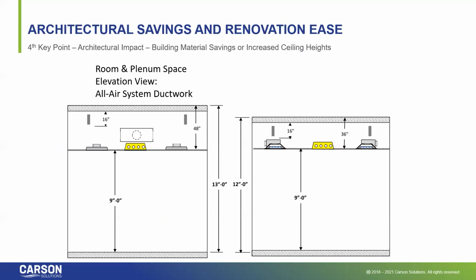From an architectural standpoint, both in renovation work as well as new construction. So in a renovation, you might not have the plenum space to renovate that with an all-air duct of 16-inch by 18-inch duct routed throughout that plenum. You just couldn't do it. But in new construction, if you want to maintain that same ceiling height that I show of 9 feet, you might be able to reduce that physical structure by 1 foot to 2 feet very easily because of the minimal duct size that's only bringing in the ventilation air.